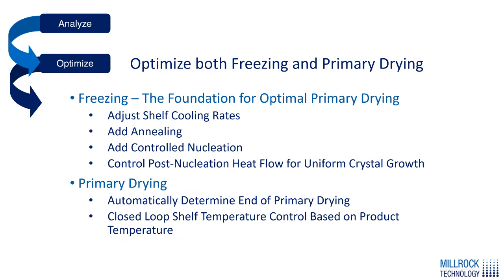Once you've analyzed your existing process, you can start to optimize both the freezing and primary drying portions of your protocol. This is extremely unique — most systems only focus on the primary drying side. However, with the technologies we provide, you can adjust your shelf cooling rates, add annealing, add controlled nucleation, and you can do something nobody else can do: control nucleation with what we call post-nucleation heat flow, where we actually control the crystal growth after nucleation.